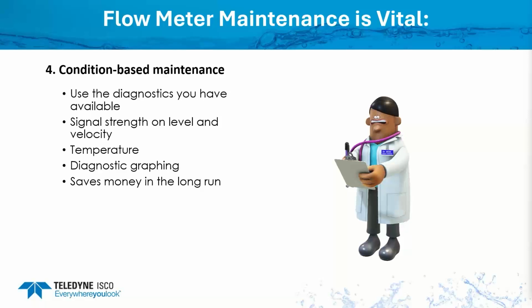As far as using the temperature, that could help determine if you're seeing added flow, it could possibly be due to industrial discharge from a boiler or washdown. If you notice your temperatures, like on an ultrasonic sensor, start to go way up or really low, ultrasonics use temperature to compensate for the speed of sound. And so if your temperature reading's off, it's going to affect your level reading, and that could result in calculating higher or lower flows. Same thing with a pH sensor. It uses temperature as well, and so your pH readings could be off if your temperature is off. So just another tool that you could look at.